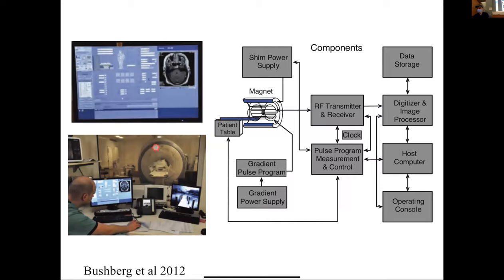Putting it all together: the magnet is in an RF-shielded room (copper walls) to prevent external RF from contaminating the signal. The operator sits outside at a console controlling the gradient and RF systems. Data is digitized and processed — in MATLAB or C — to reconstruct images.